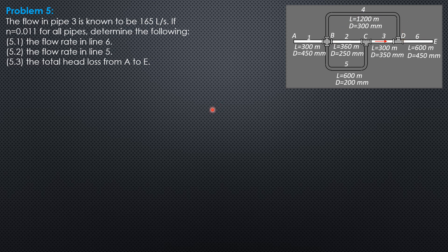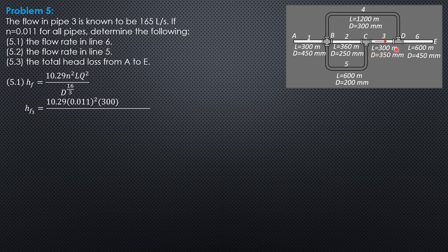The procedure for analysis uses the formula: HF equals 10.29 N² L Q² over diameter to the 16/3 power. Computing the head loss in line 3: HF3 is 10.29 times 0.011² times 300 times 0.165² over 0.35 raised to 16/3, with diameter 0.35. So the head loss in pipe 3 is 2.747 meters.